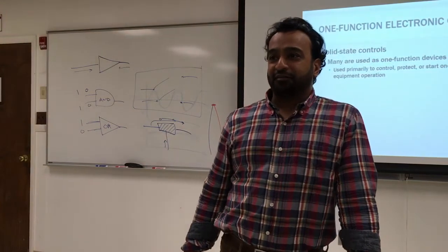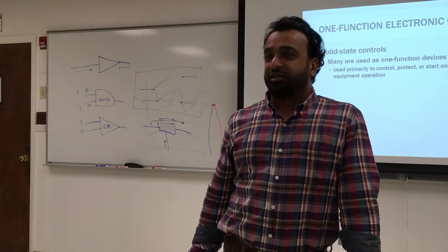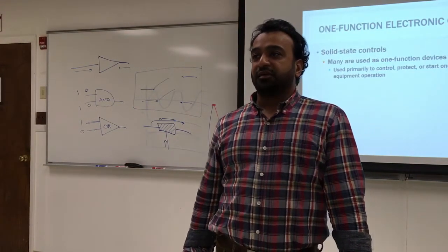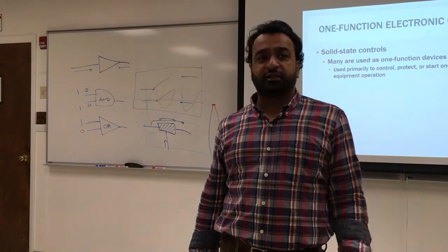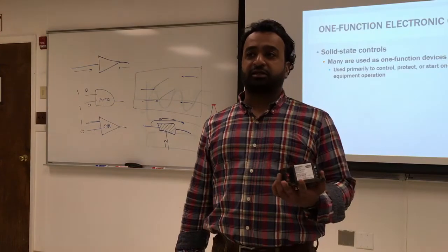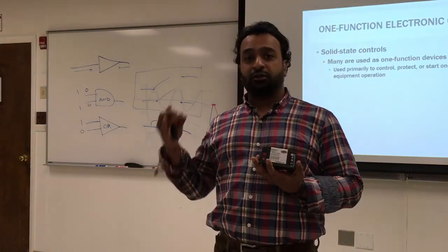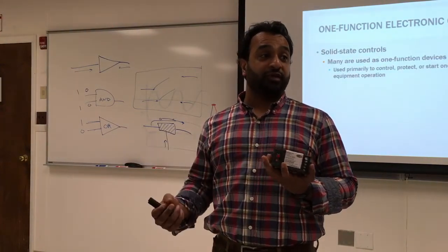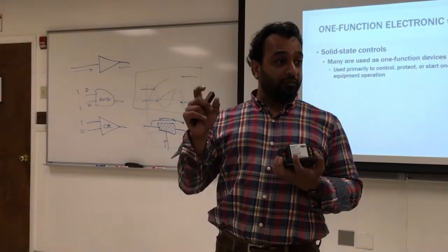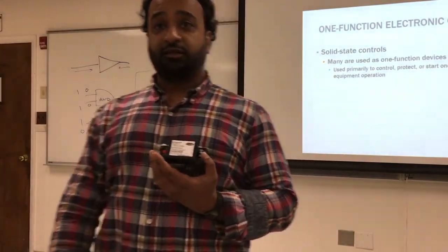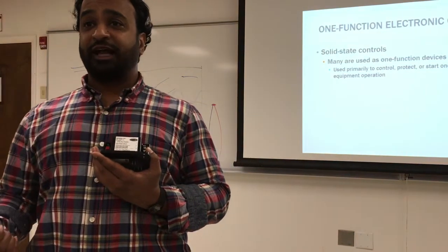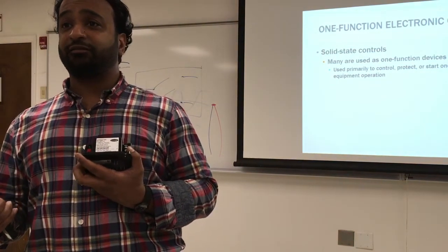Sorry about interrupting, but on the digital readout ones, it does that all automatically. Yeah, that's the fourth generation. I love it, it's awesome. It's only about $140, but it tells you everything. What I like is it says it's in standby now, trying for ignition, flame proven. And it gives you the strength of the flame based on the ohms. So it reads the ohms. The stronger the flame, the less the ohms, because the CAD cell resistance in the dark is very high, right?